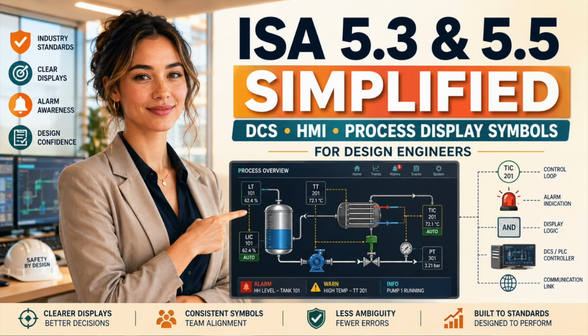This is where many projects go wrong. They begin with a piping and instrumentation diagram and attempt to fit the whole drawing onto a monitor. Every valve, reducer, drain, vent, line number, and instrument bubble is transferred because it already exists in the engineering document. The result may be technically complete and operationally useless. The operator does not need to continuously see every engineering detail.